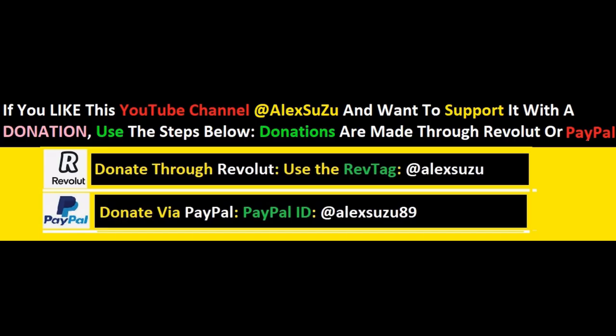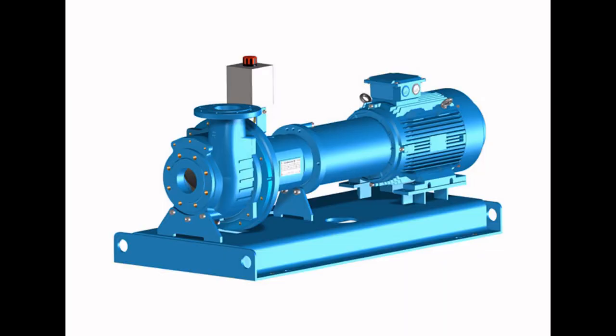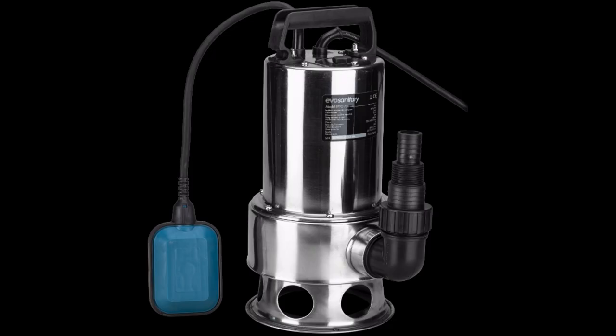Submersible pumps. They are completely lowered below the surface of the water, immersed in the liquid, which they push to the consumer. As such, they have the following advantages. Being installed below the frost limit, they are implicitly protected from the danger of breakage due to the freezing of the water in the pump body. They do not need priming. Being immersed, the water enters the pump body, which only pushes the water towards the consumer. There is no more absorption, so they are more efficient. Much reduced noise compared to surface pumps.